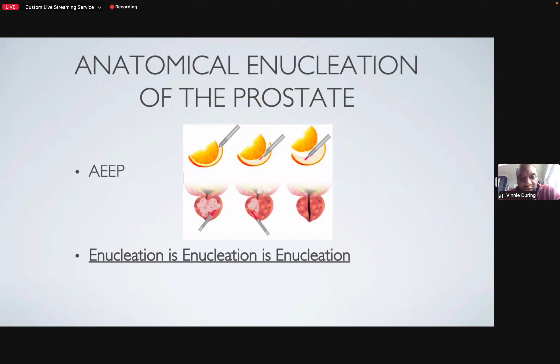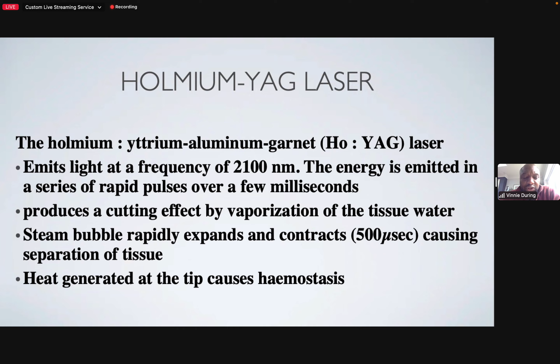The holmium laser is a pulsed laser that emits light energy at a wavelength of 2,100 nanometers. It produces different effects depending on the distance and the power settings when applied to tissue. When in close contact with tissue, there is a direct cutting effect. However, most usefully for soft tissue enucleation, at a very short distance, these pulsed energy bursts produce a bubble which rapidly expands and contracts and causes separation of the tissue, acting as a blunt dissector in much the way that the finger does in an open operation. There is also heat generated locally, which leads to hemostasis.